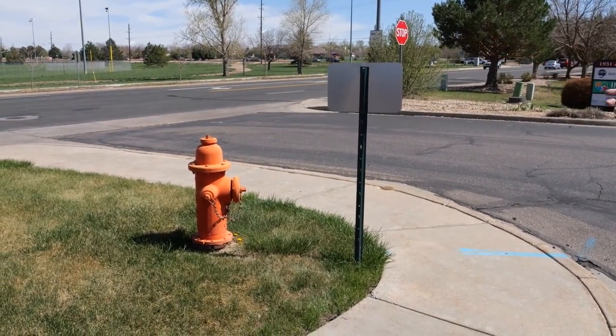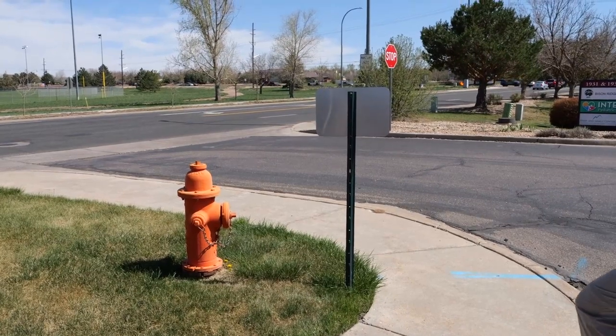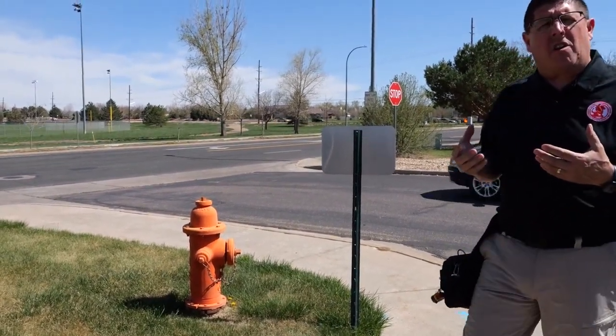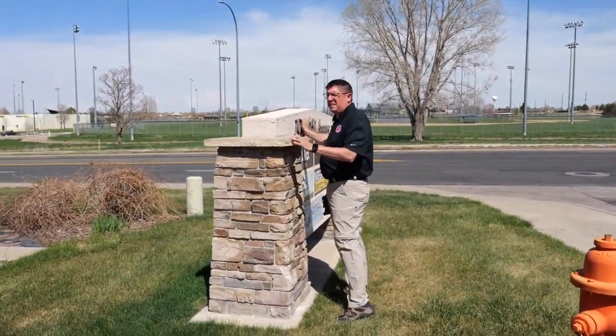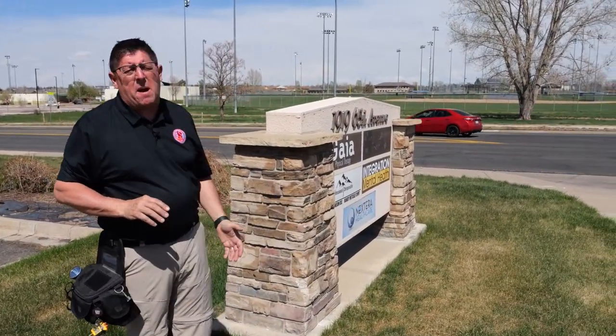This one is wide open right in the middle of landscaping — that's excellent. The second important exterior item is signage. I don't care about the tenant's name, but is the address of this building visible from the street? On this large sign I've got numbering on both sides — 1919 — so even from a distance, as a fire apparatus or emergency vehicle comes up, they'll be able to see the number. That's really important.